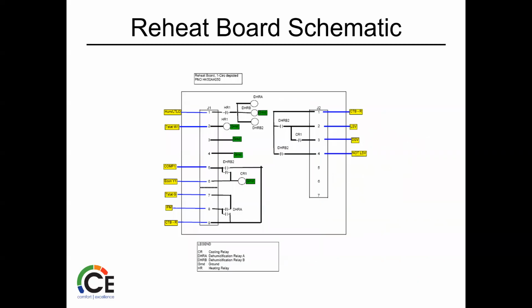So we talked about that reheat board. Again, that's just a secondary board that's going to control dehumidification. There's a relay in it. So once the signal comes in for dehum, it's going to operate the reheat board. That's where you're going to turn on, if our RSVs or whatever we've got are tied in, depending on the unit. We get the signal from Y1, we get a T-stat G call, we get an indoor fan operation, CTB powers us, so we get R from the control board, and then humidifier operation on that jumper.